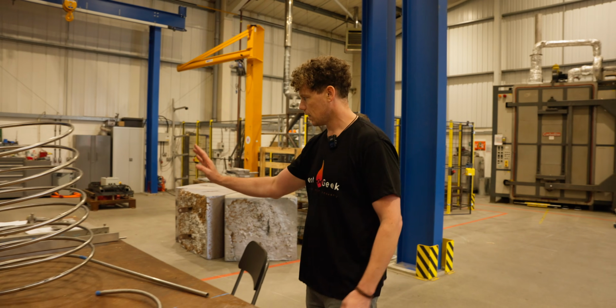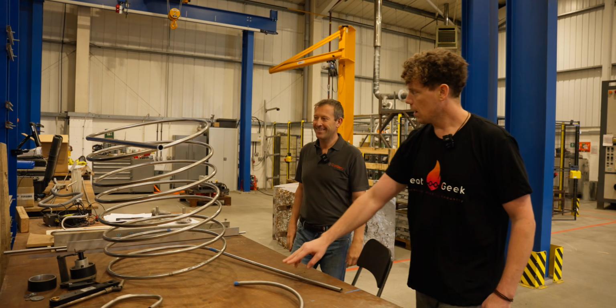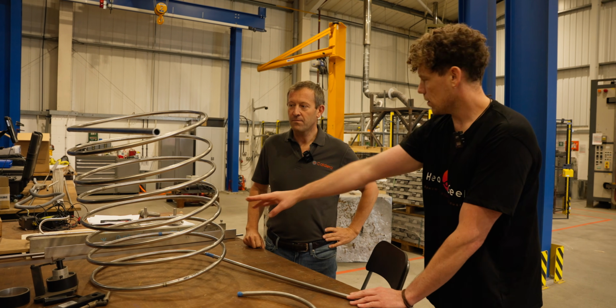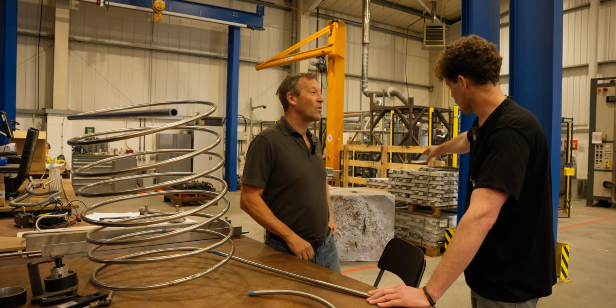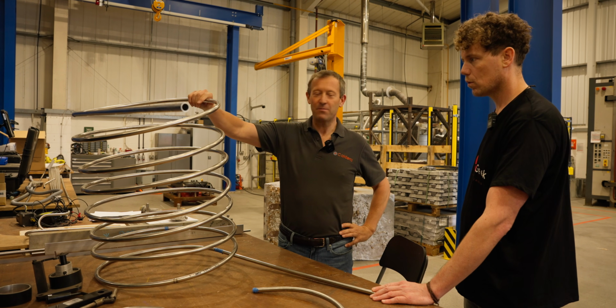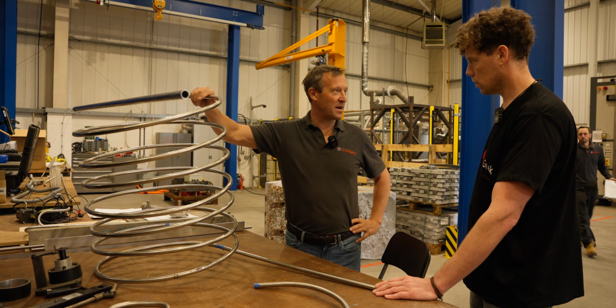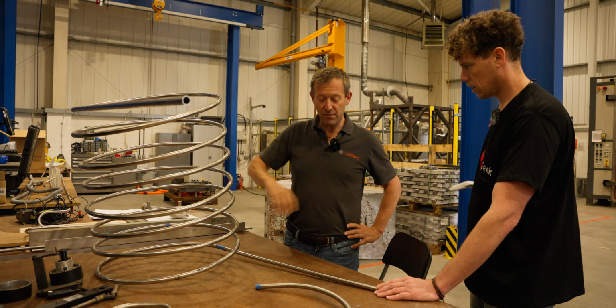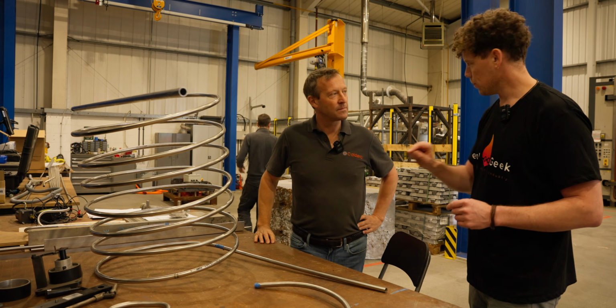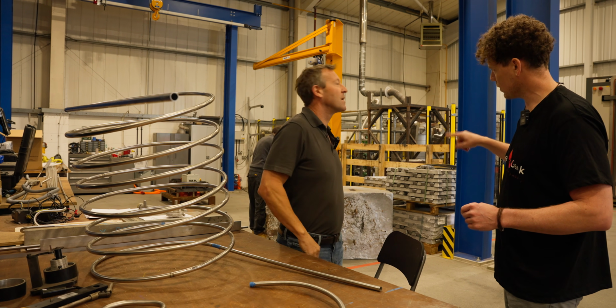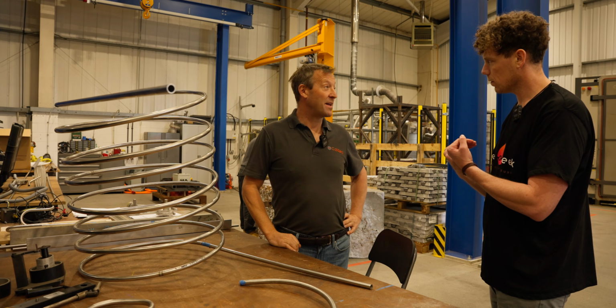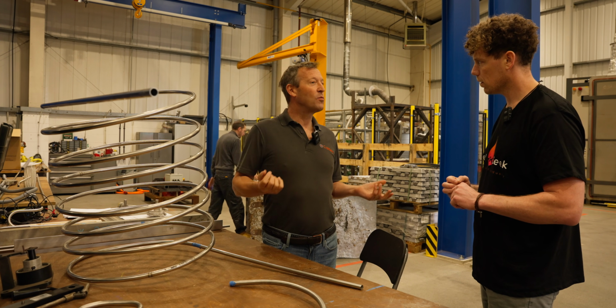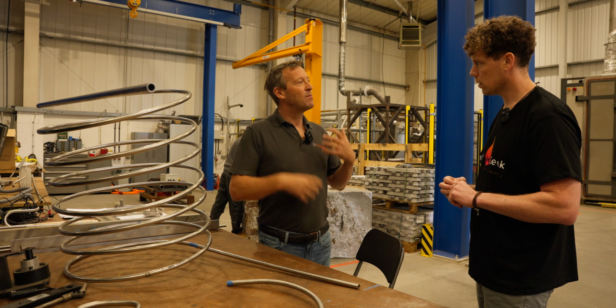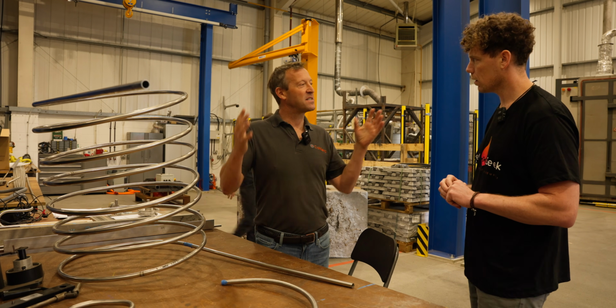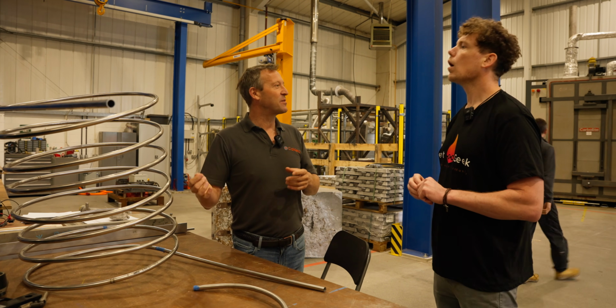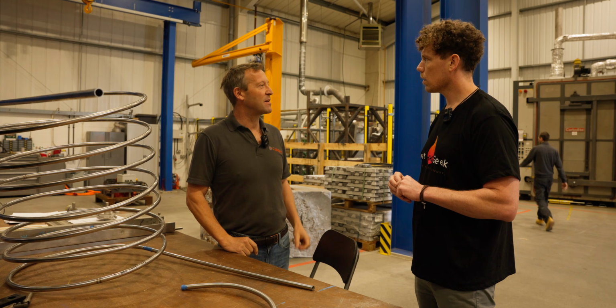This heat exchanger here - is this the size of a coil per wedge? So we fit one of these per wedge, and it's made from a single piece. Are those linked together in series or parallel? Depends - they're normally linked, at least some of them in series, but it depends on what the customer wants, because you can change the amount of power we get out by changing whether they're in series or how many are in series versus parallel.